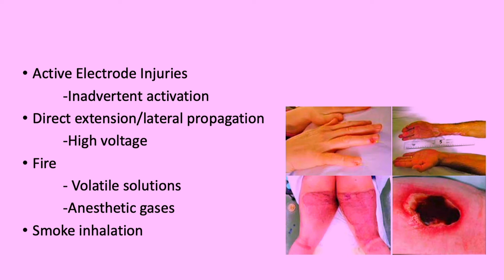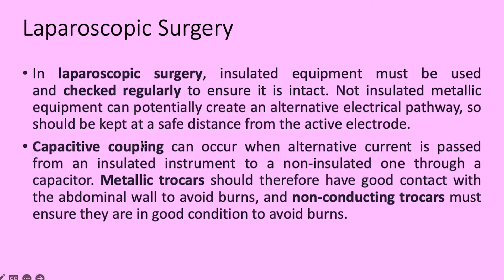Other injuries can occur through inadvertent activation of the electrode, or through continuous use of high voltage. There can also be fires from volatile solutions and anesthetic gases, and smoke inhalation for both theater staff and the surgeon. Capacitive coupling is more of a problem in laparoscopic surgery.